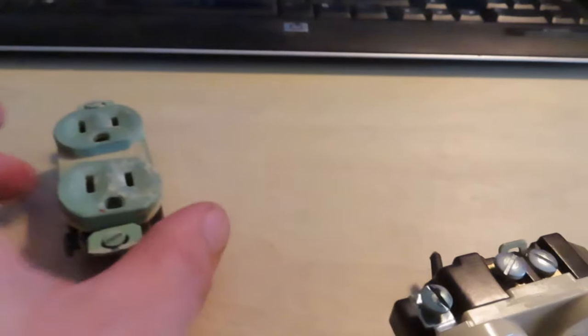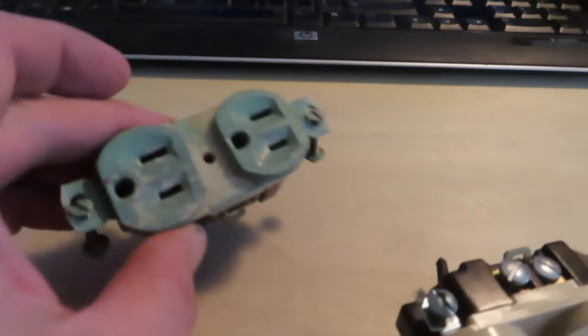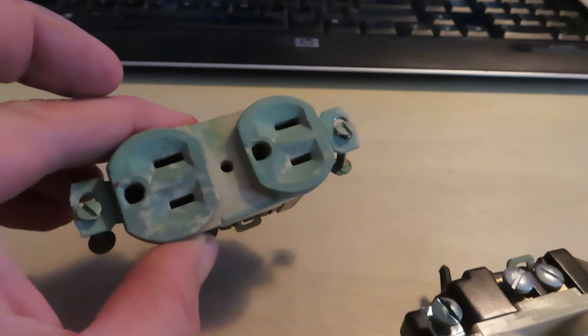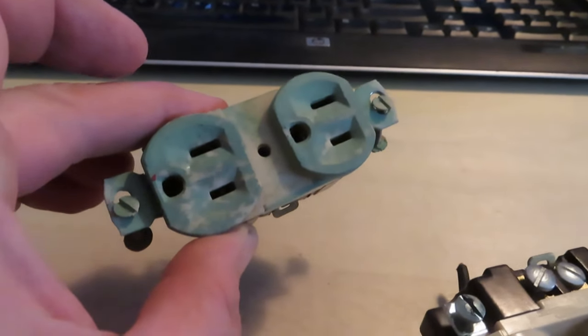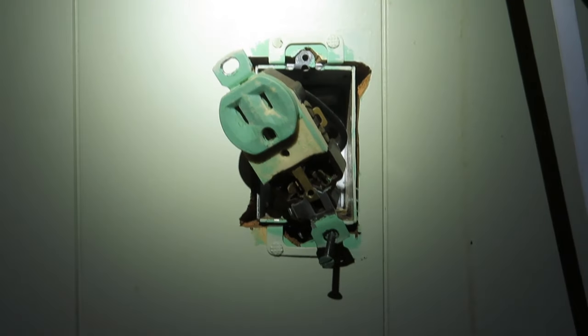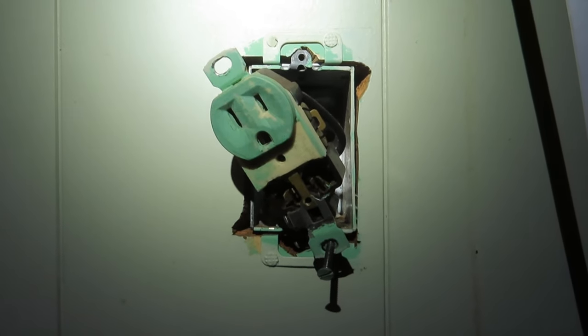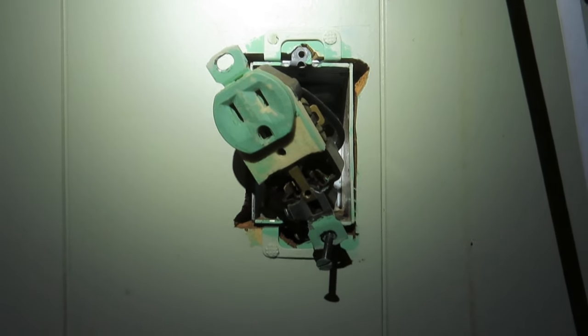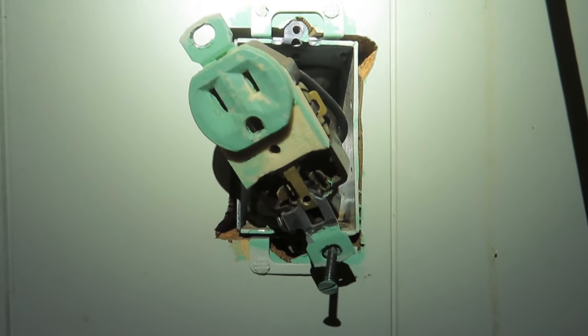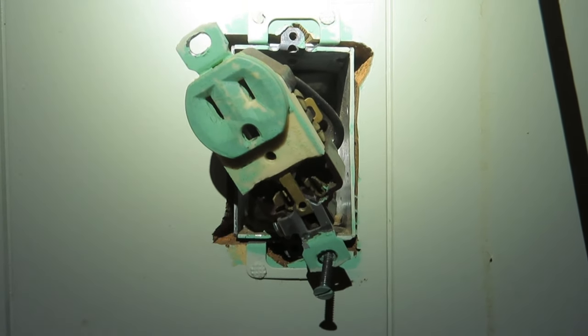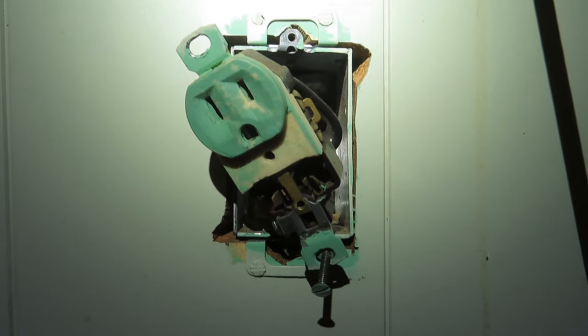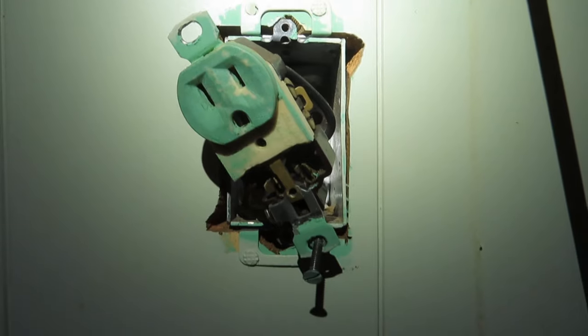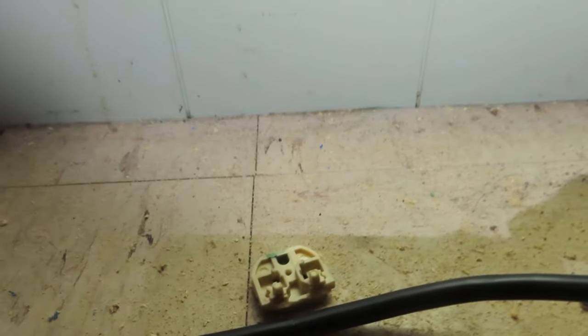I'll show you actually what happened when I took this one apart. You can see the bad situation here. This one, that's where I had my computer plugged in. I noticed it felt a little bit loose. I wanted to take the cover off, and the plug, part of the plug there, fell off. But this is the problem here that I found.